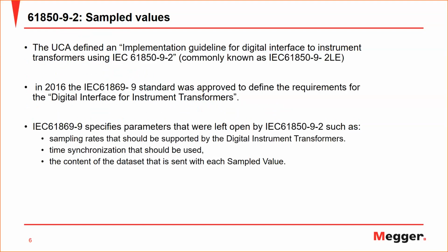The light edition, as I mentioned earlier, was introduced to help simplify things, because the abstract standard that was defined first was leaving too many things open and a lot of moving parts, so people felt it was very difficult to agree. And one of the main objectives of IEC 61850 is to create interoperability between different vendors and also to be future proof. So it left that open for future proofing, but interoperability was mainly covered by the light edition. And as well in 2016, the 61869-9 improved on the requirements of the light edition by adding more profiles to it.